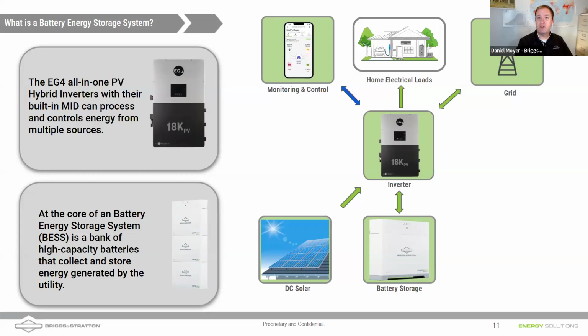We could export to grid, earning a 1-to-1 credit for every kilowatt hour we export, use up that credit at night or in the winter, and then have an annual true up. The reality is that in a lot of states, most notably Illinois right now, that idea of having net metering has gone away. We've gone to a net billing tariff, which means that we can no longer export and receive full credit. We get a wholesale credit.